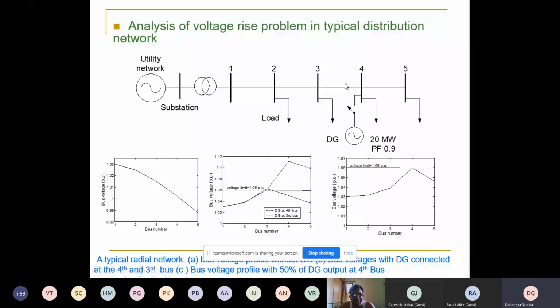Now another important thing: connect this generator at the 3rd bus. You can still see a voltage rise problem at the 3rd bus, above the limit—the voltage is still going up. But notice the effect here is lesser. So the observation is: as the DG connection point moves closer to the substation, the voltage rise effect becomes lesser. Of course, it depends on several factors, but it becomes lesser—that's an important observation to make.